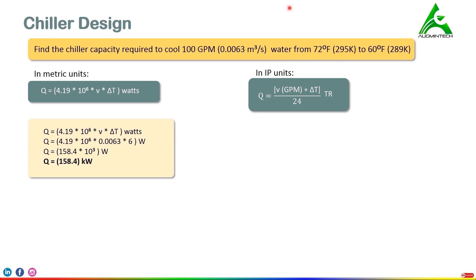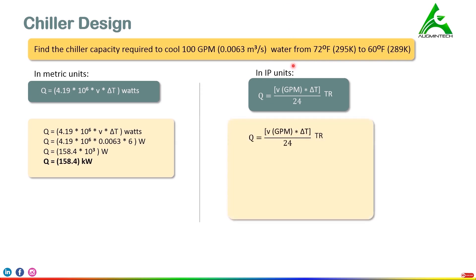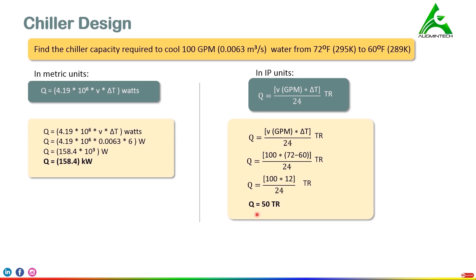Now let's solve the same problem in IP units. We substitute V = 100 GPM. The temperature changes from 72°F to 60°F, so delta T = 12°F. Using the formula: 100 × 12 divided by 24, the final answer is 50 tons.